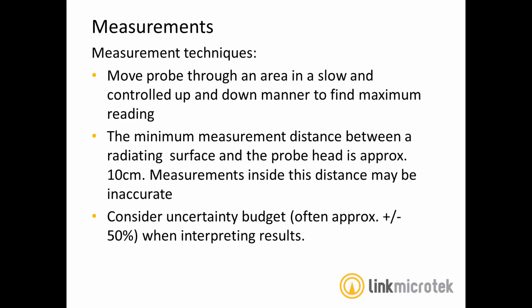This last point about uncertainty budget is important. If you've got your measurement equipment from a reputable source, you'll be able to take readings at face value, and you don't need to worry too much about uncertainty because the manufacturer has in effect sorted it for you. But if you've purchased equipment with an inadequate specification, you'll have no idea of your uncertainty budget, and you could easily be out by a factor of 10 or more either way, which could make your measurements worthless.